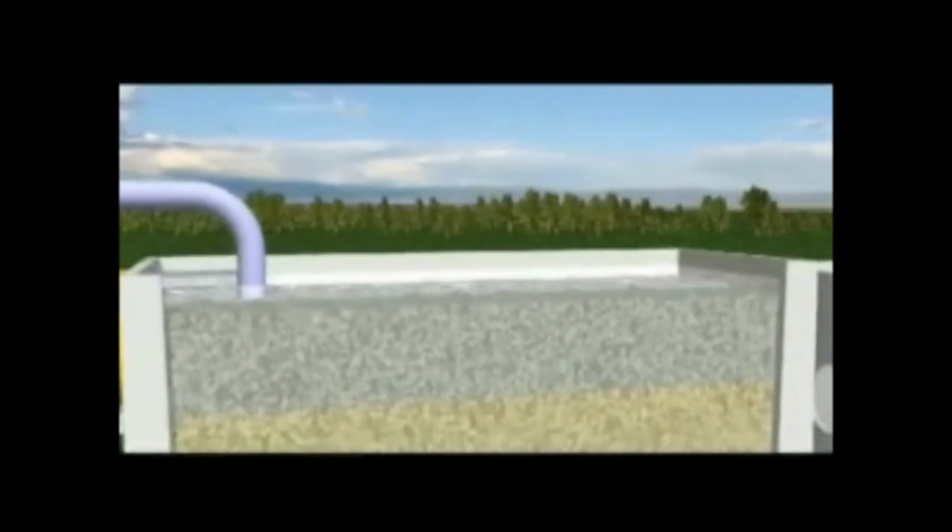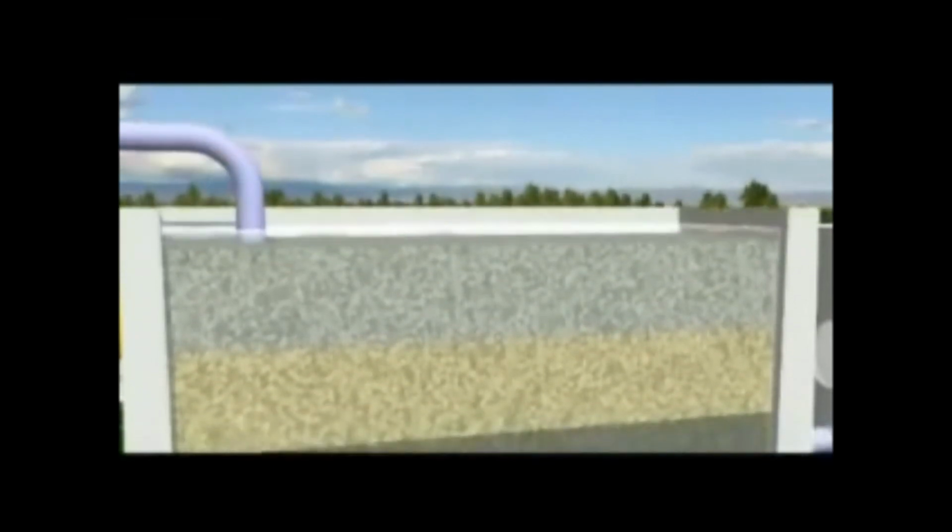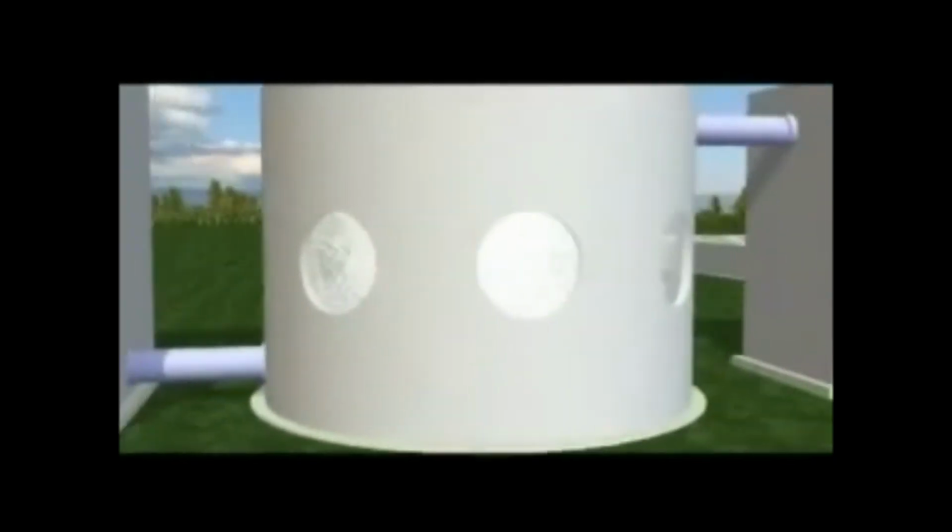The water now needs filtration to get rid of any remaining particles. Water is filtered slowly through very fine sand or sand-like material. For some river waters, we use ozone gas injection as a treatment stage. This can work in conjunction with GAC, or granular activated carbon treatment, where the water is filtered through carbon granules to take out any undesirable traces of largely natural organic materials. The carbon in these filters is removed and regenerated by heat, so it can be used again.